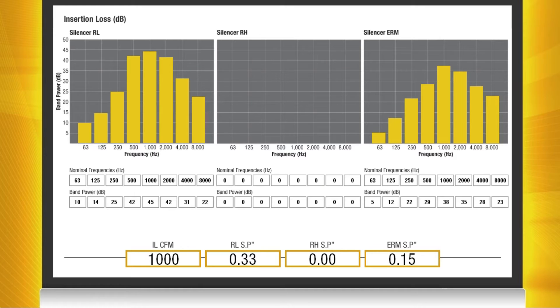With the RL silencer we're getting high insertion loss performance with a relatively high pressure drop and this has to do with the baffle configuration of that silencer.